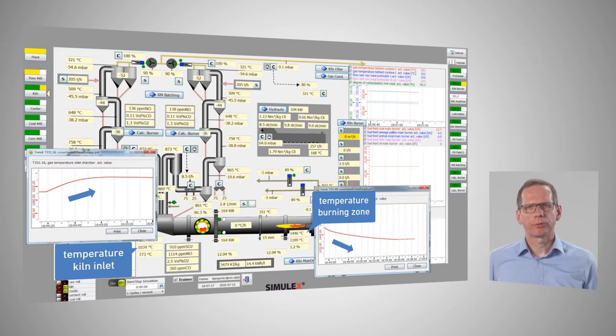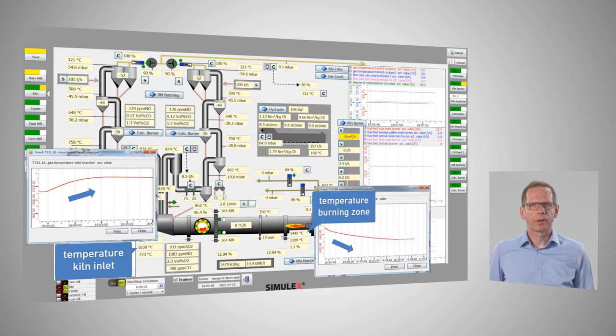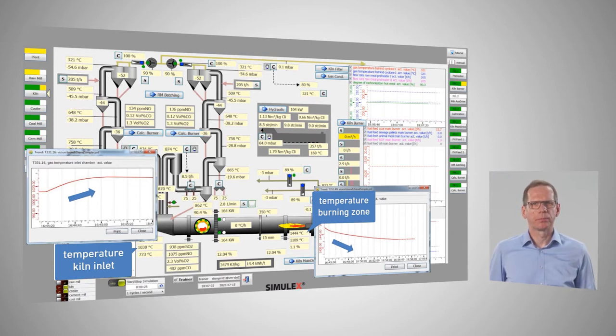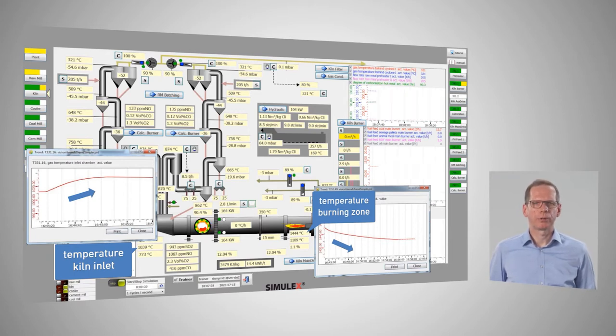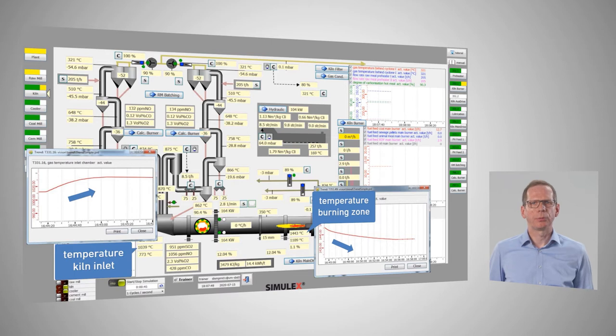Let's see what happens after changing both parameters. We see a rise in back-end temperature and a slow cooldown of the burning zone — that means the quality of our production is getting worse. At the moment there is still enough oxygen available to compensate that effect due to additional fuel feed. But as soon as the excess air is consumed, we need to increase the air intake to be able to maintain the desired heat profile in the burning zone.